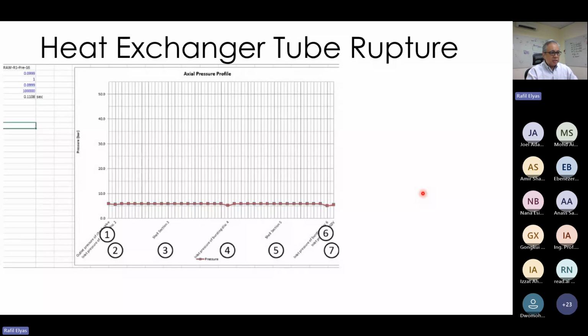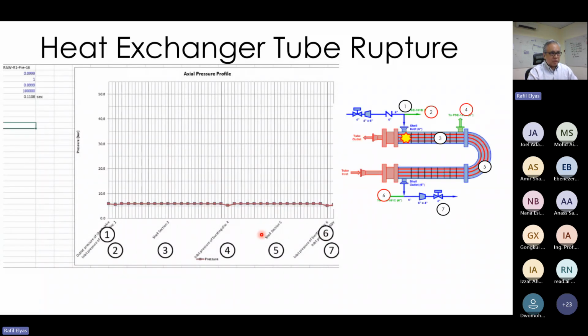Okay, so here's an example. In this case, I've modeled this shell and tube exchanger. I've plotted out the profile here, and I'm inducing a rupture at the inlet. I'm plotting these locations across the exchanger: one is at the inlet piping, two is at this location, 3, 4, 5, etc. I've got relief valves placed in various locations here as well, and a bursting disc. This simulation happens very fast. If you watch the timing, it's happening within less than a second. So let's see if I can run this animation.